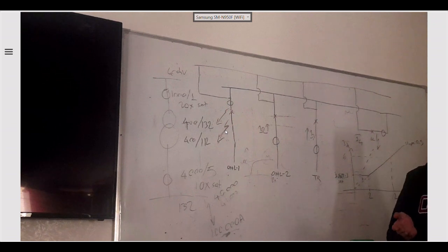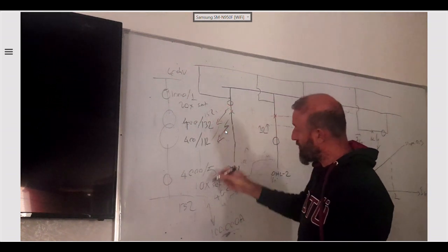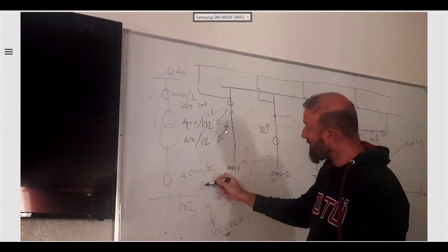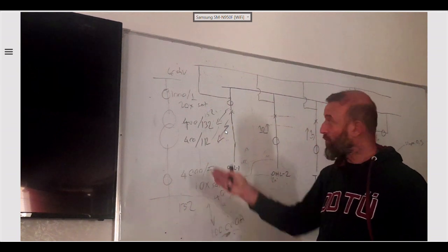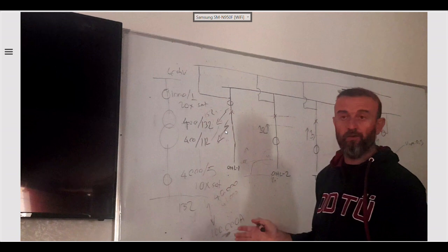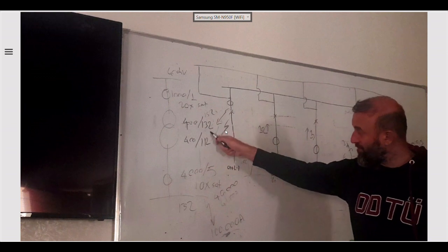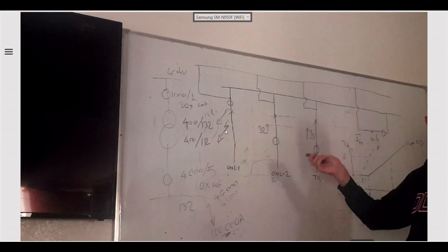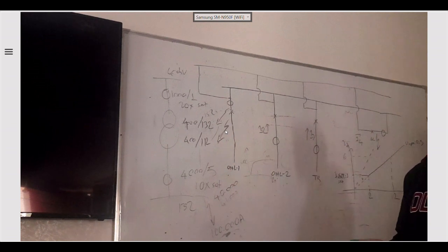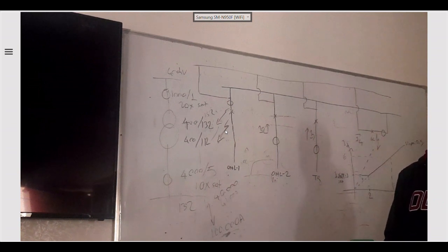Maybe what he is saying to you is that there is a general result of some tests in the world that the tap position is in between 152 and 132, and the saturation is in between, for example, 10 times to 20 times, and they might calculate an average value for them. But in reality, our calculation department should be careful about this value and the saturation value, and they give us the value accordingly. We cannot just write, okay, slope is 2.5, slope is 0.5, whatever. If we don't have a calculation department, then we have to trust the recommendation of the Siemens manual.